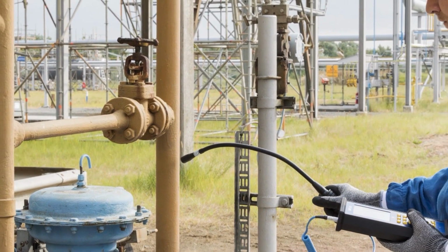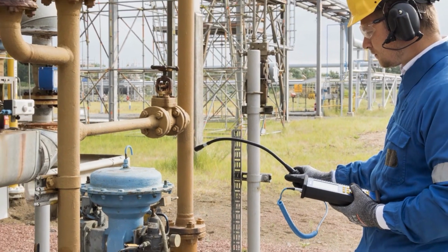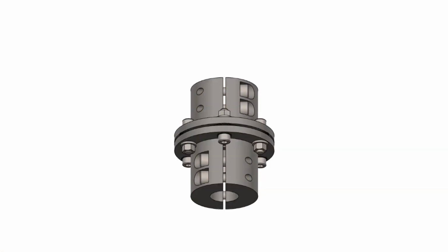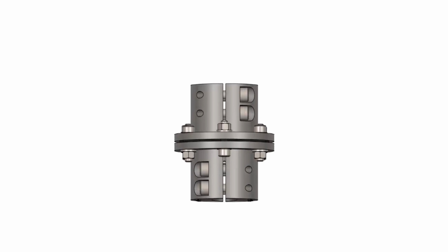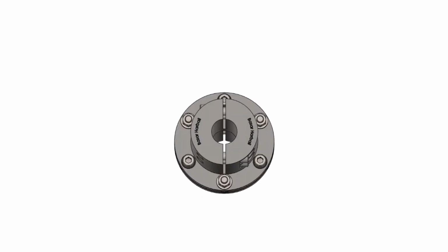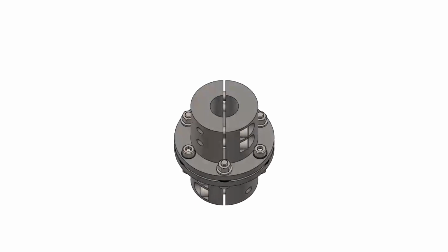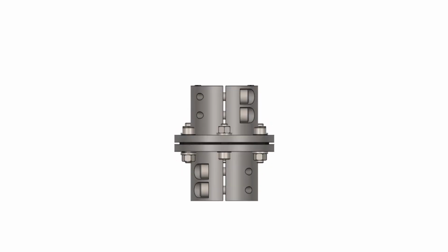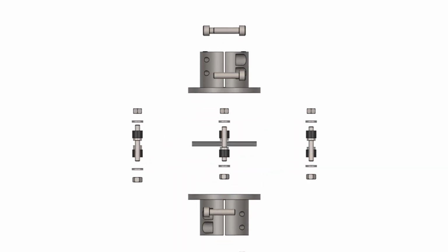There are a lot of flanged couplings used in heat exchanger condenser systems. Finding vacuum or pressure leaks here is challenging because the leak rate is minimal, turbulence is captured and dissipated in the crevice of the flange, and the ultrasound sensor can't get close enough to hear the leak, especially in vacuum.